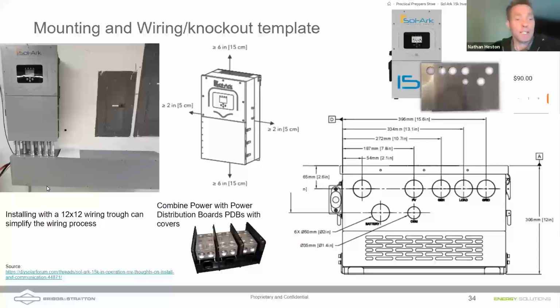I recommend installing this with a wireway. A 12 by 12 wireway will get you all the way out. You can squeeze by with a 10 by 10 wireway. And the nice thing about that wireway is it just gives a nice clean look, and it makes it easy to run your wire, gives you some room as well. So I mentioned before using these power distribution blocks to do combining. If you need to combine, you can get these in very large, 500 amp blocks if you're wanting to use these as combiners for batteries as well.